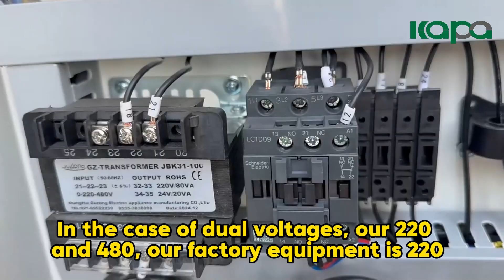Now we confirm the terminals. Terminal 21 corresponds to 0 volts. Terminal 22 corresponds to 220 volts. Terminal 23 corresponds to 480 volts. At this time, we can see the wiring. We know 22 corresponds to 220 volts. How do we change it to 480?